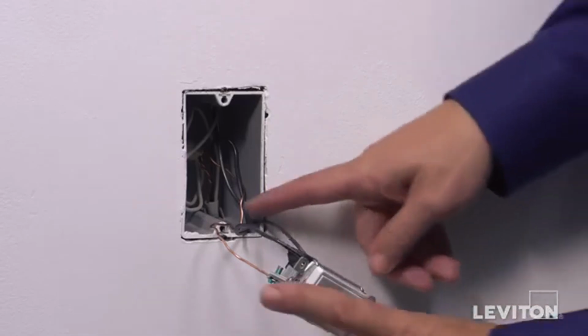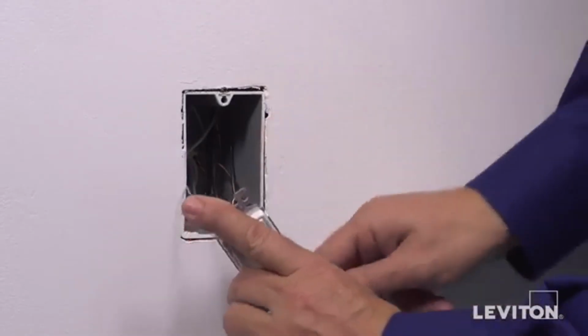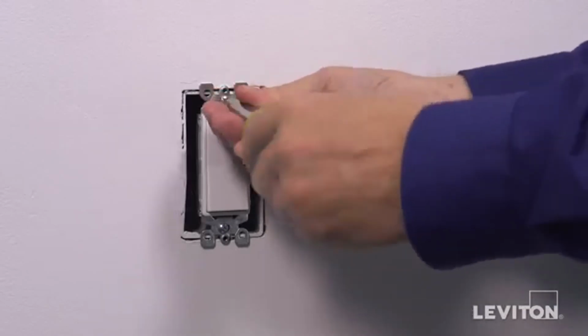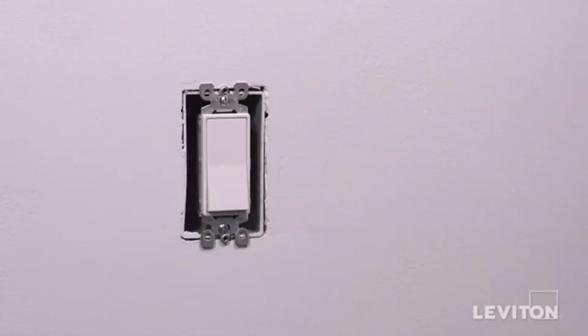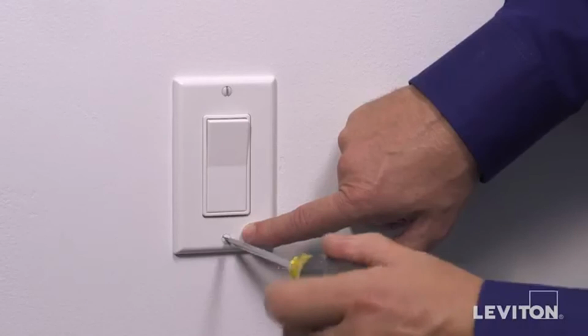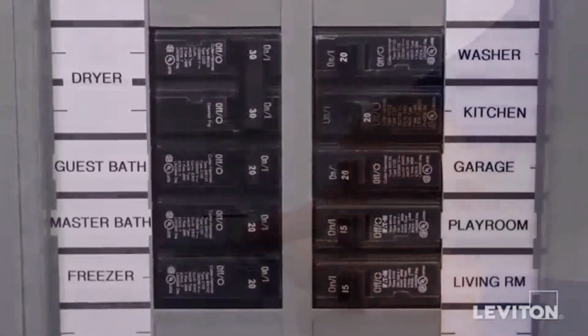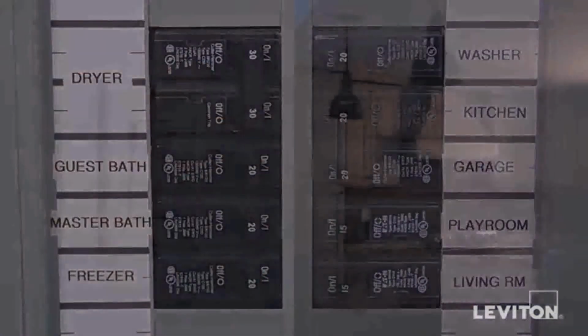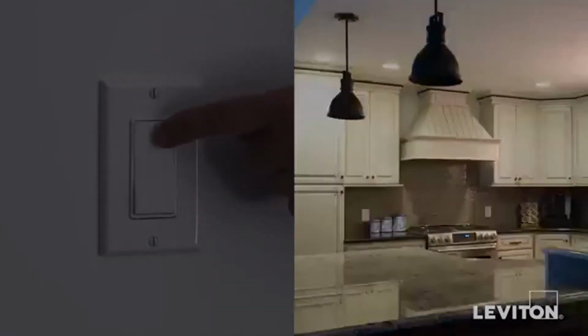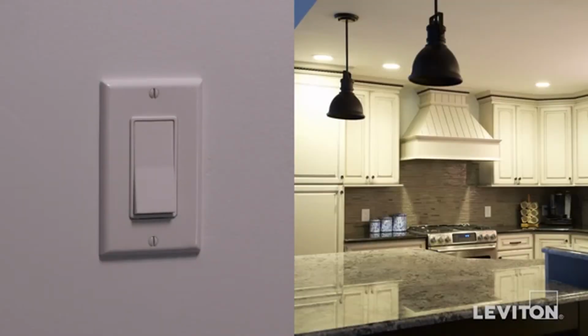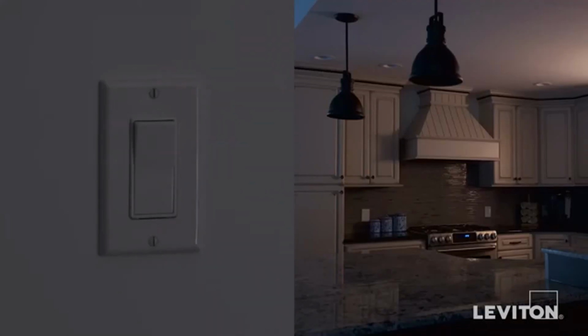Carefully position all wires to provide room in the wall box for the device. Mount the device in the wall box with the mounting screws provided. Attach the wall plate. Restore power at the circuit breaker. Test the installation by operating the switch several times. The lights should turn on and off.